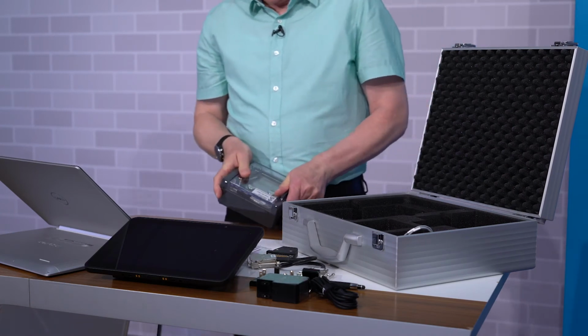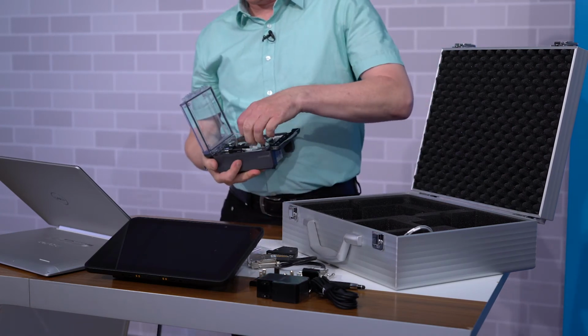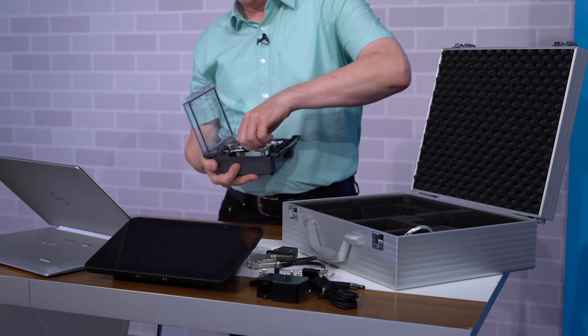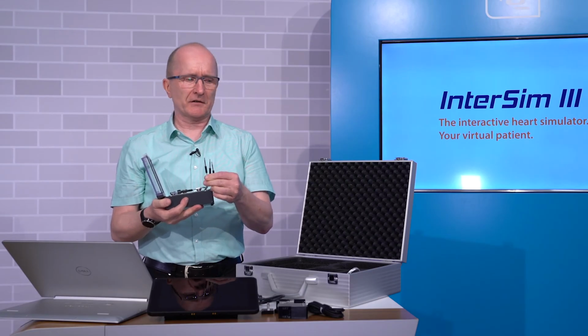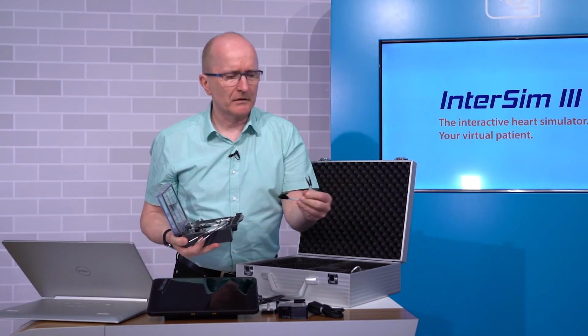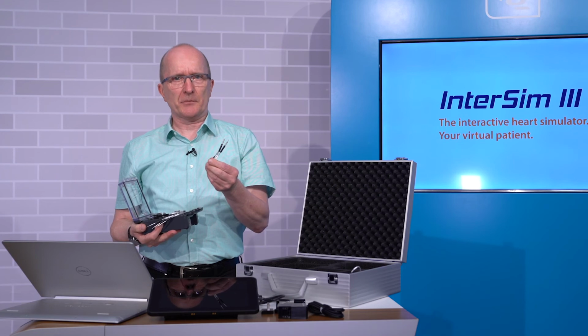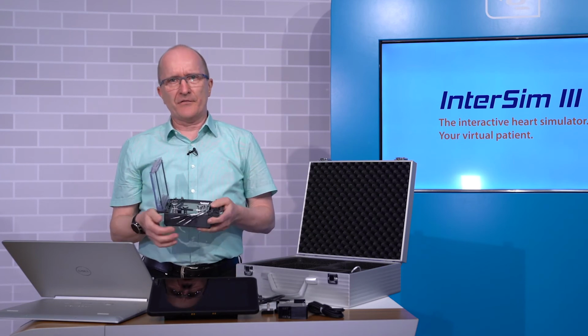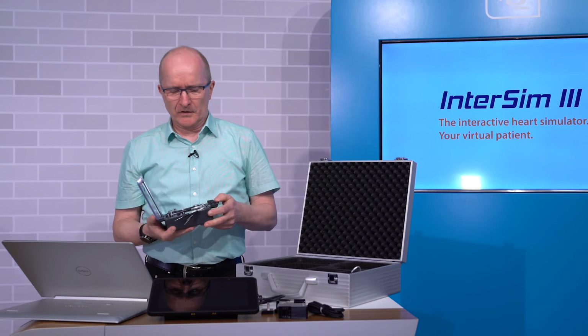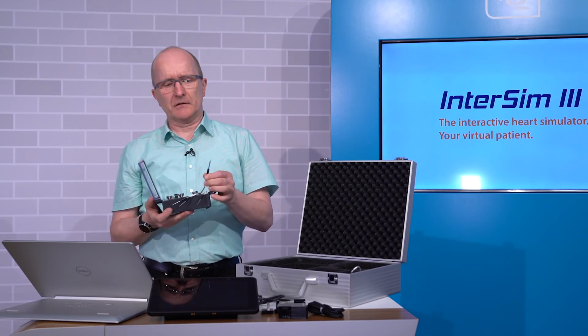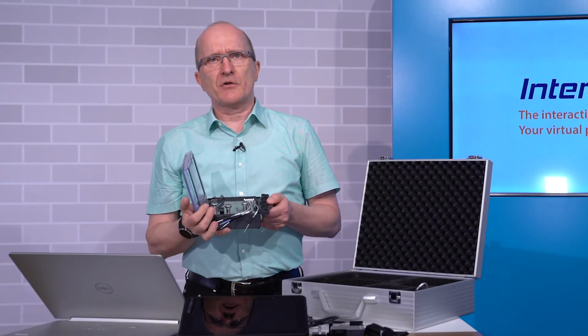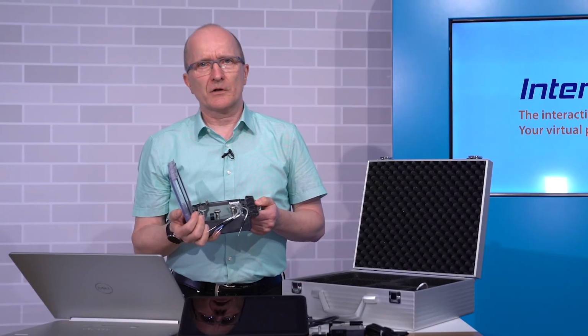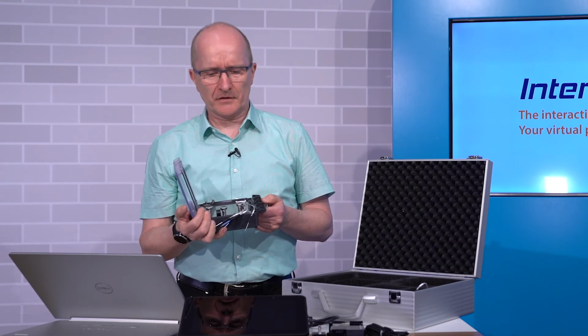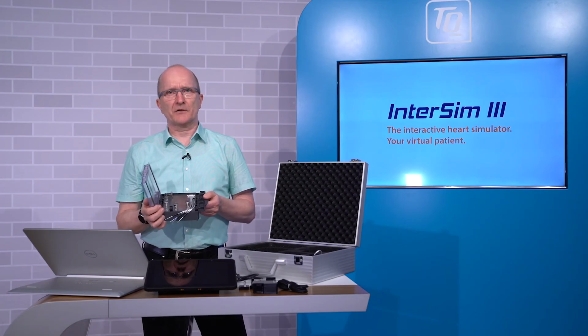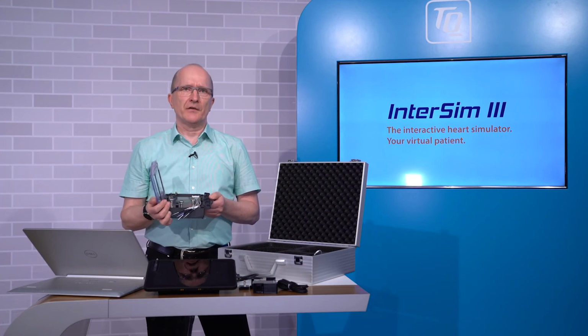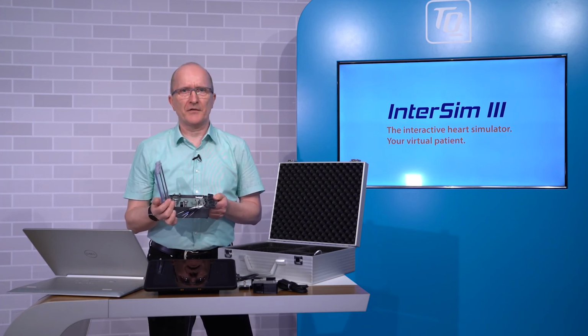The standard adapter box is connected with 3 IS1 connectors and 1 DF1 high voltage adapter. Since I have an extended adapter box here, my box has an additional IS4 connector. This way you are able to connect IS4 quadripolar devices to the adapter box. The additional IS4 connector is the only difference between the standard adapter box and the extended adapter box.